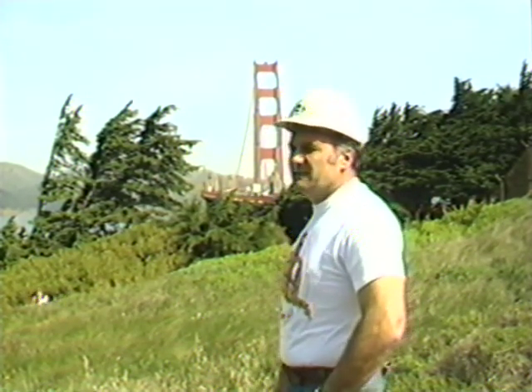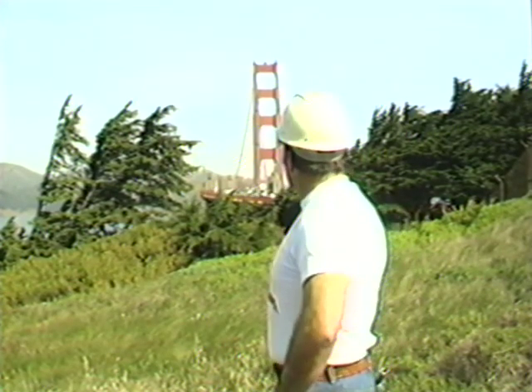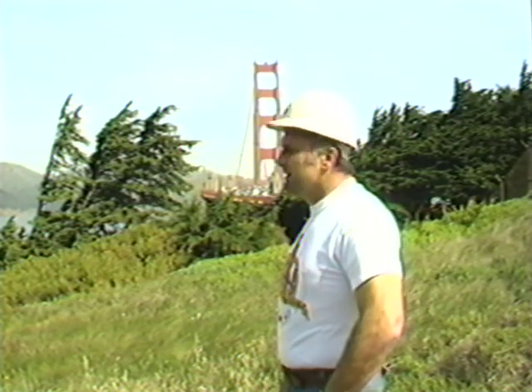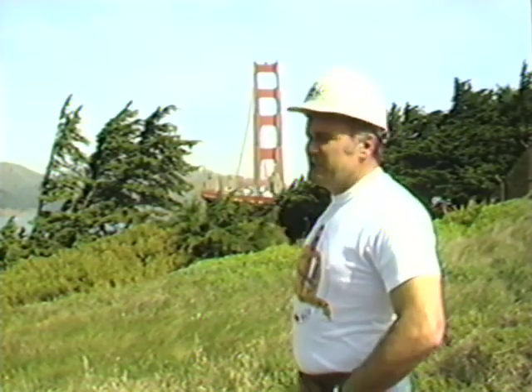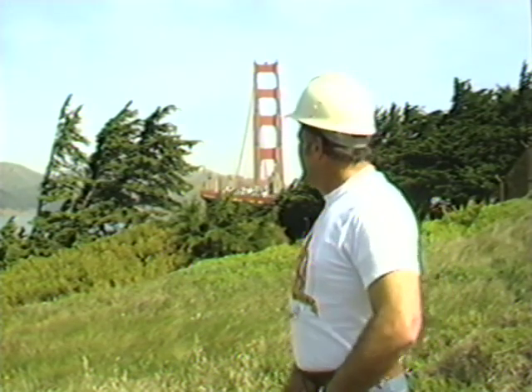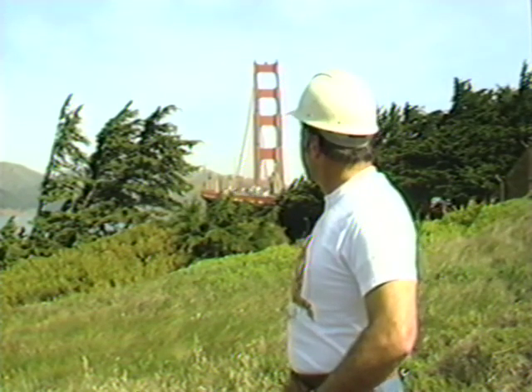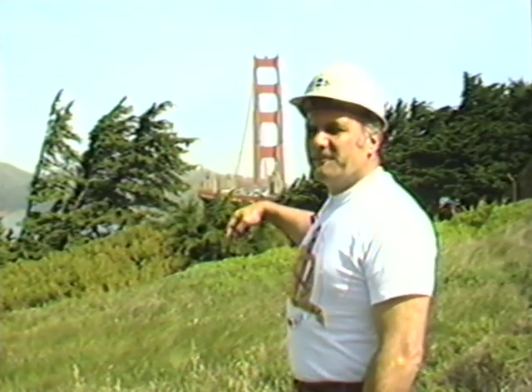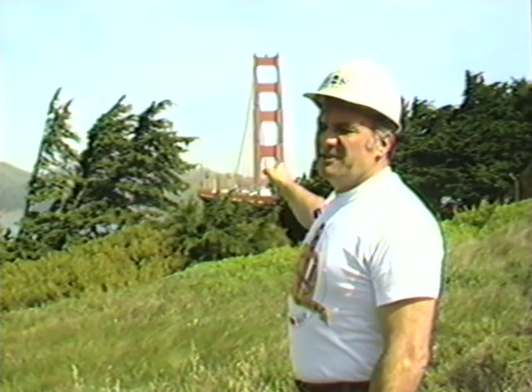If something goes wrong with the beacons at night, the electricians are required to go up there and make them function. They are aircraft beacons, and they have to be functioning at all times. If the horns go down, the operating engineers have to come out here at night and work on them. Fortunately, now we have backup systems on the horns, so we don't have to come out as often as we used to. We have new horns that we just installed this year also, a newer type with less maintenance, and the electricians have completely rewired the system, so it's a little easier. We used to have to climb down over the side at midspan, go down the ladder to the bottom, and physically turn the horns on and off, whatever time it was, middle of a storm, whatever was going on.